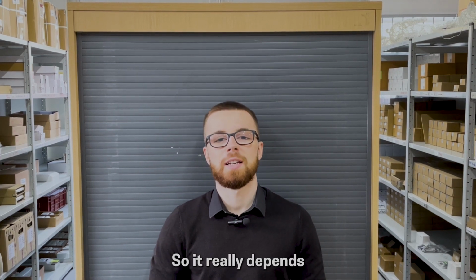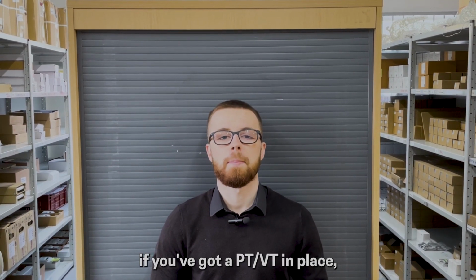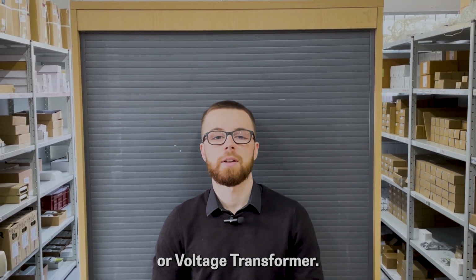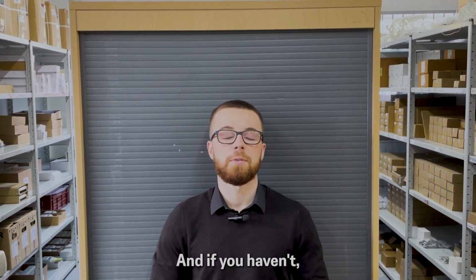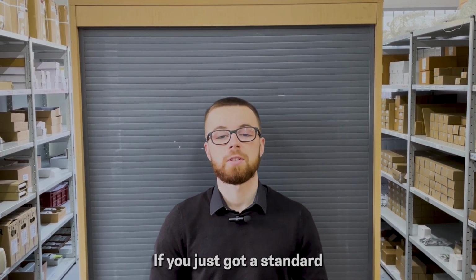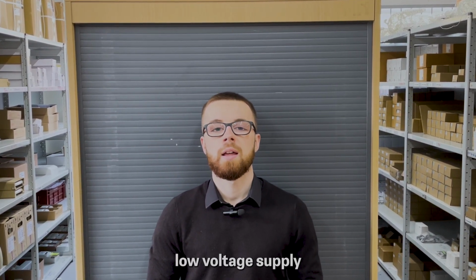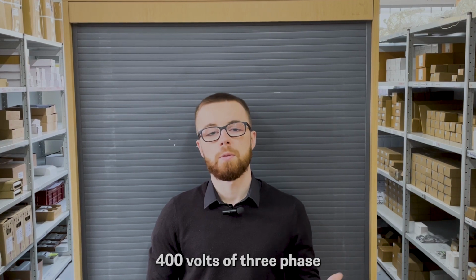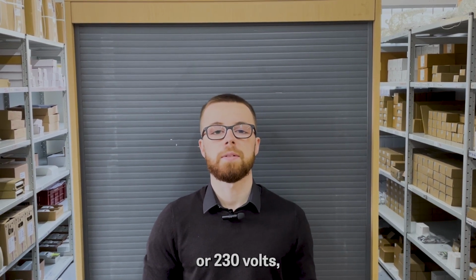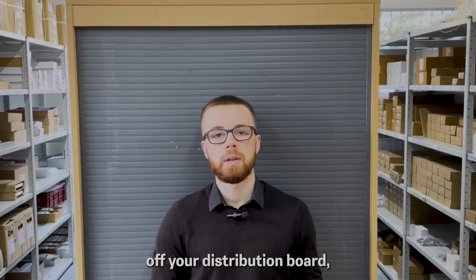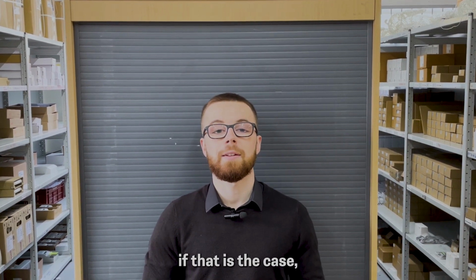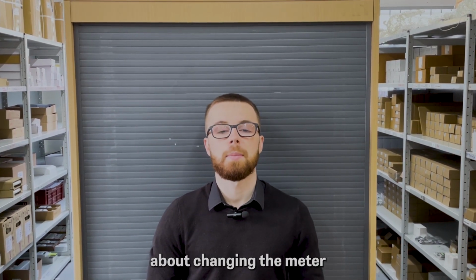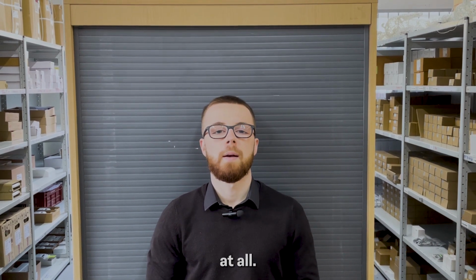So it really depends if you've got a PT, VT in place, which is power transformer or voltage transformer. And if you haven't, then you don't need to worry about this. If you've just got a standard low voltage supply and you're pulling 400 volts for three phase or 230 volts for single phase off your distribution board, then you've got no issues. If that is the case, then you don't need to worry about changing the meter at all.